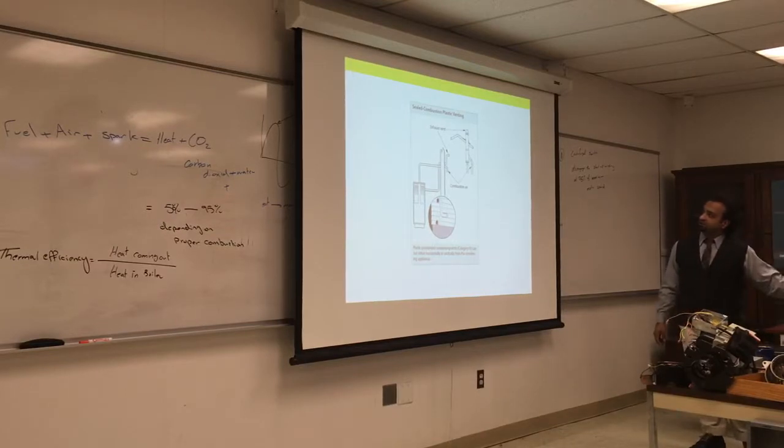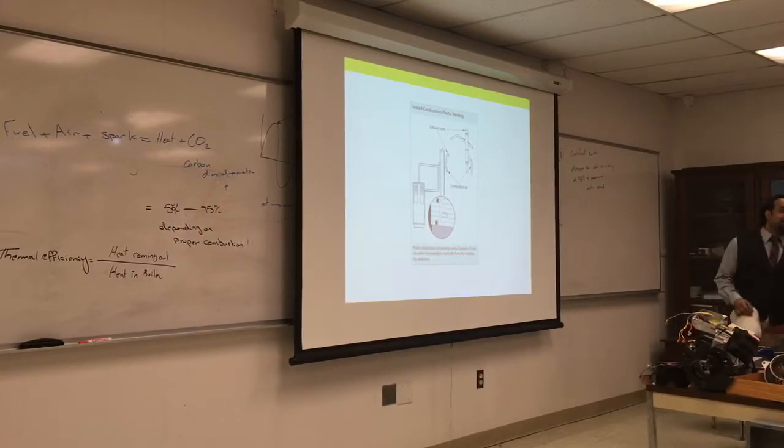Sealed combustion venting. Again, if we are using a condensing boiler, we can use plastic for the vent, because what is the temperature at the vent? 60 or 70 is very low, so it's okay. Are they all gas or oil? Both. I've seen both. But to be honest, I think gas is better for this kind of application because it makes it a little bit more convenient.